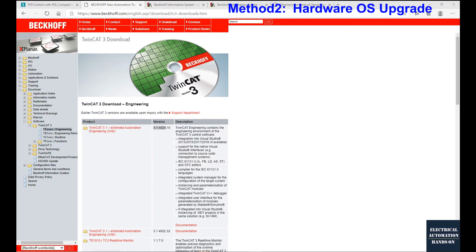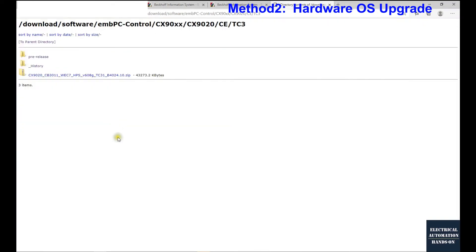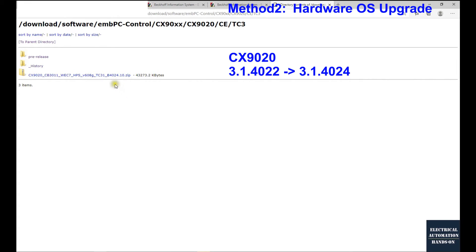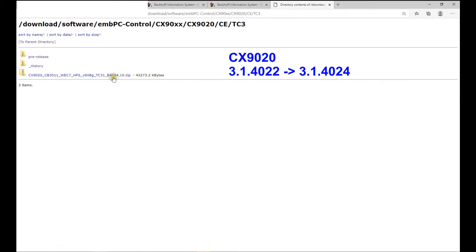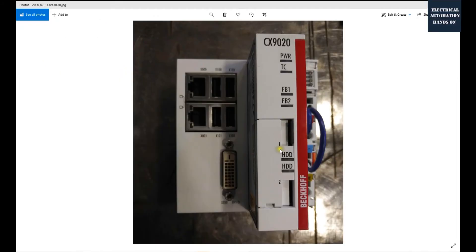To upgrade the hardware to the latest main version 4024, first contact your local Beckhoff support and ask them to send you the OS image that matches your hardware and latest software version. You may be able to download it from the Beckhoff FTP, or support will provide a special download link. Be careful to get the correct file — downloading the wrong file and loading it into your controller could crash the controller. In my case, my controller is the CX9020 and I need to upgrade the OS image from version 4022 to 4024.